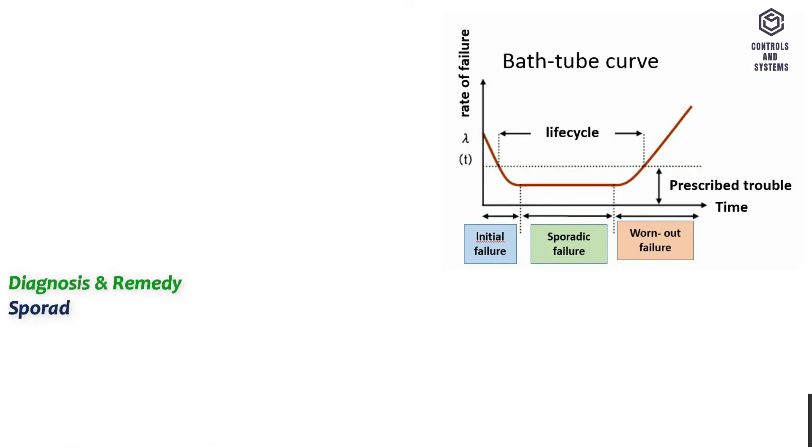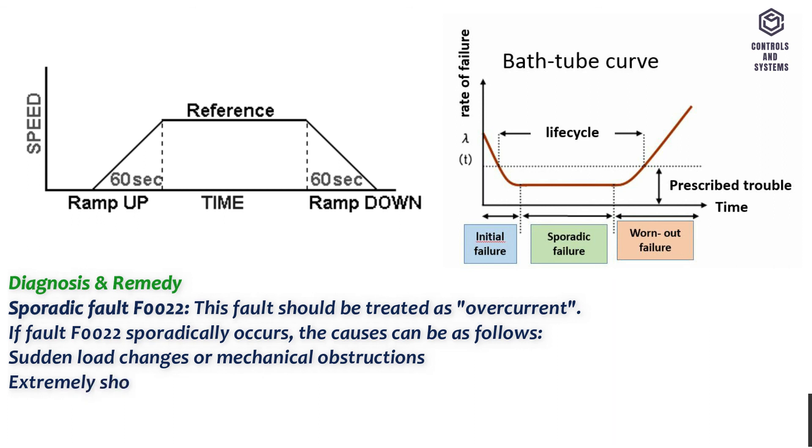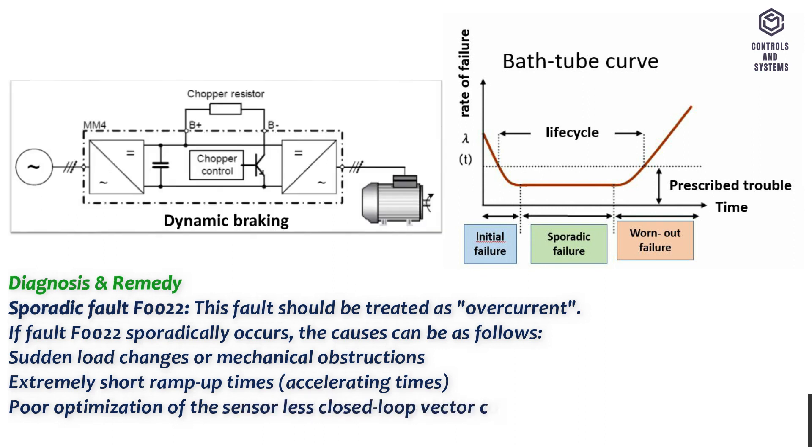Sporadic fault F0022: This fault should be treated as overcurrent. If fault F0022 sporadically occurs, the causes can be as follows: sudden load changes or mechanical obstructions, extremely short ramp up times or accelerating times, poor optimization of the sensorless closed loop vector control, incorrect braking resistor is installed with an excessively low resistance.